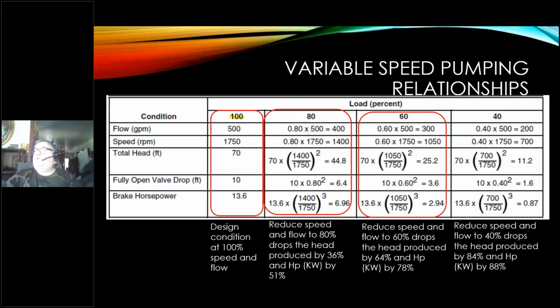Now, if we really get down to the low end, 40% speed and flow, the head produced, again, what it can accomplish, pumping this amount of water against that resistance, we've dropped from 70 feet to 11.2. 11.2 is mighty low. And again, this is why I question operating below this point, because really, your system is still your system, and 11.2 feet isn't much. And the horsepower is now down to less than 1 horsepower.